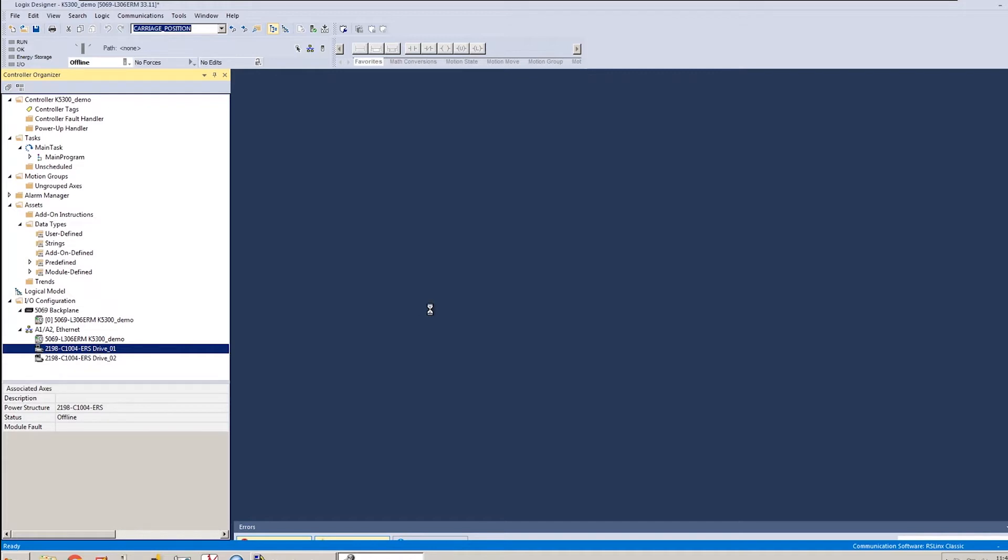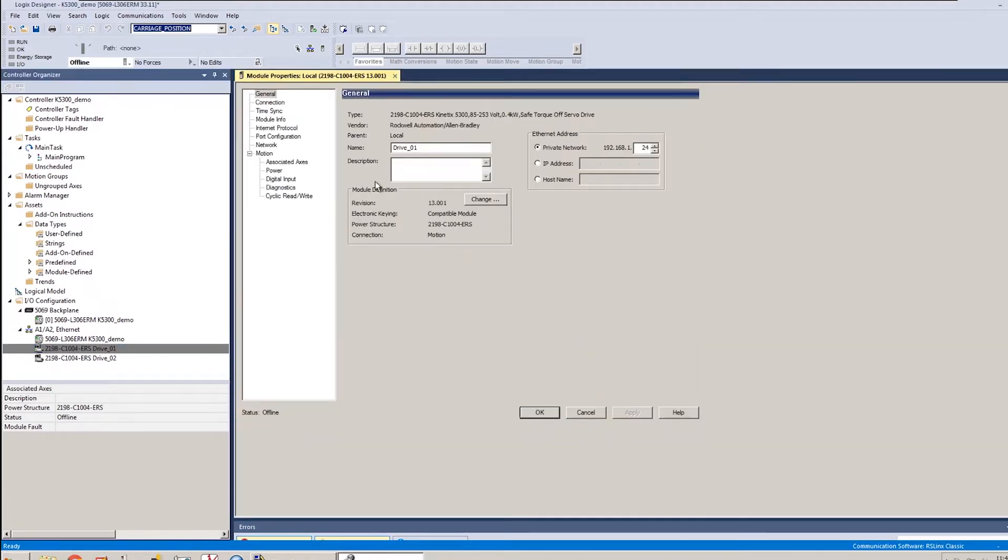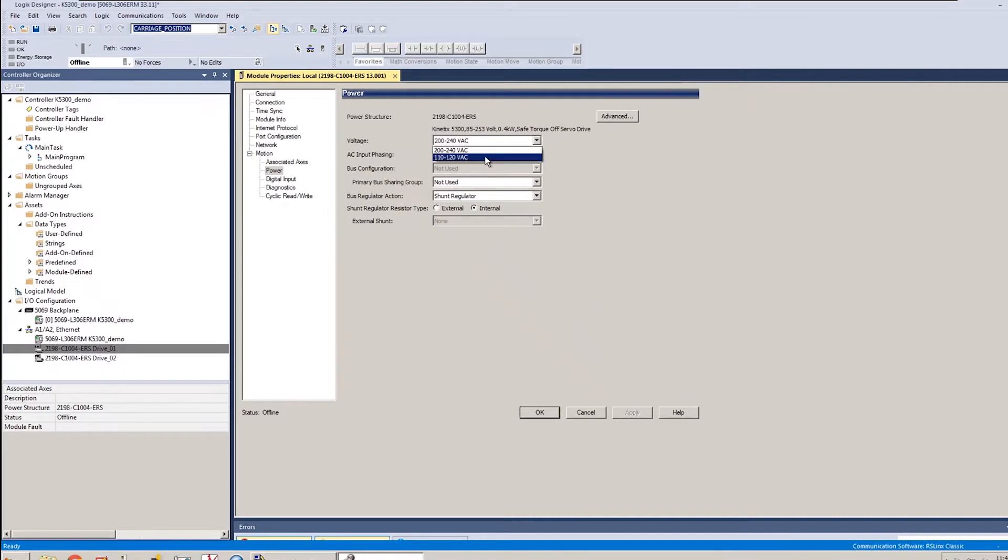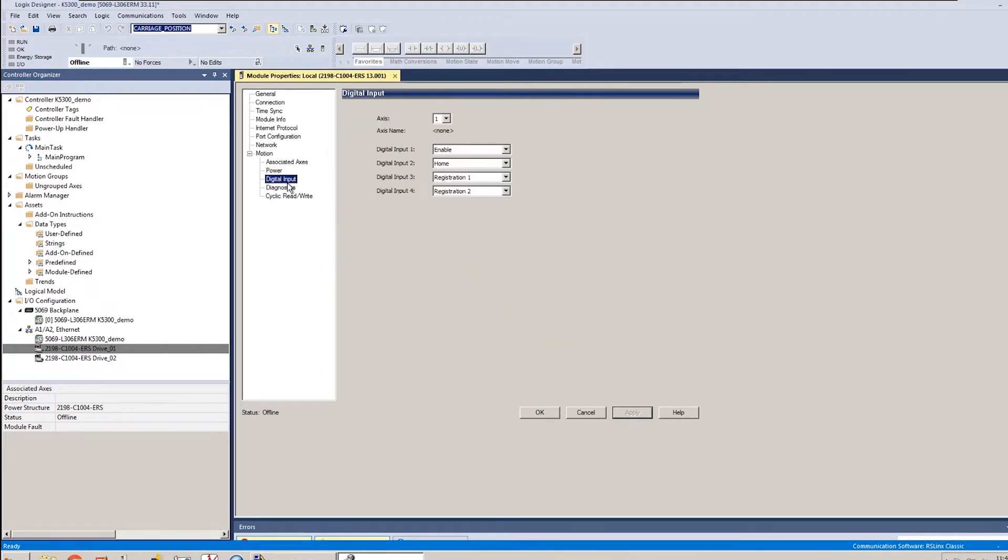And the first thing that we'll change is we'll go into the power settings and configure the drive for the correct voltage and phase that we're using today. So on the power tab, I'm going to select 110 to 120 volt, single phase, I'm going to leave all the shunt settings as internal, and apply those settings.